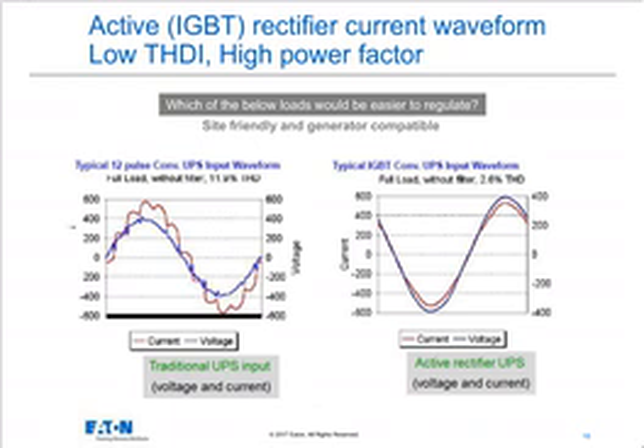with older style UPSs, in this case with a 12-pulse rectifier. That's the waveform on the left. The red waveform is the distorted current. And if you look closely at the blue waveform there, you see the notch and ring style distortion that was very common there. The current total harmonic distortion was around 12%, and it needs to be down around 5 to 7% in order to be acceptable.